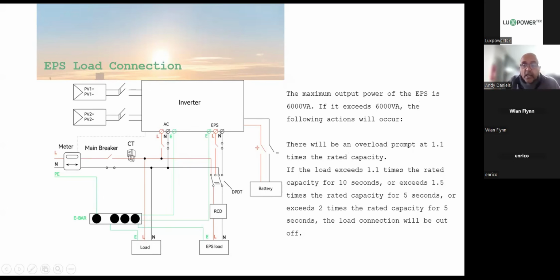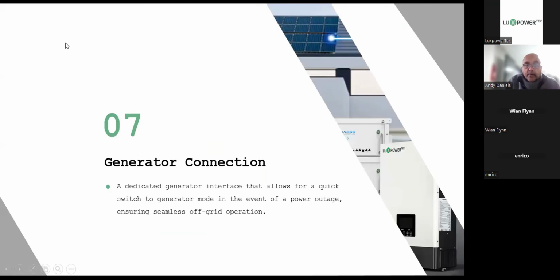We'll see that on a motor or a pump startup. We have a surge current coming through, it can handle that. 5 seconds, then the load will be cut off and you'll get an EPS overload. Okay, so remember that. We do allow for these rating times for startups. All right, the generator port or the generator connection.